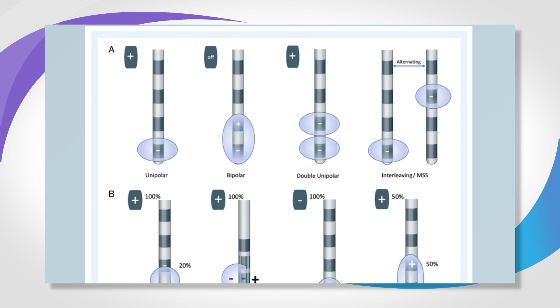You can also have two separate programs on the same electrode alternating between each other, and that is called co-activation. Here it's labeled as interleaving or multi-stimulation. In this B section, it's showing a virtual contact. On the Boston Scientific device, we can use two adjacent contacts together, and the stimulation field between them is like a virtual contact. So it's sending stimulation between the two contacts.